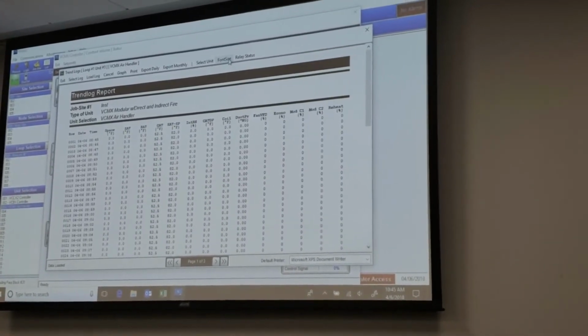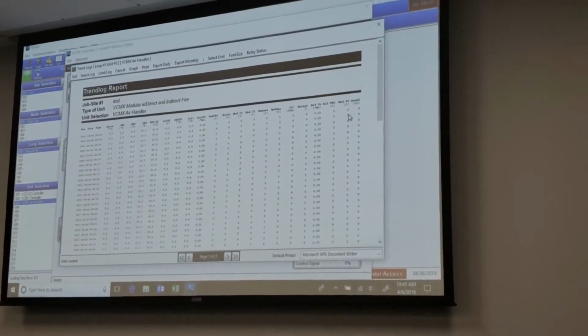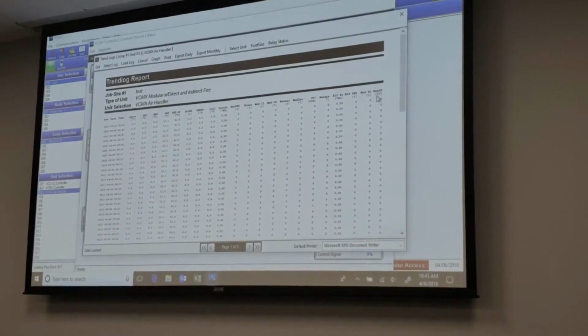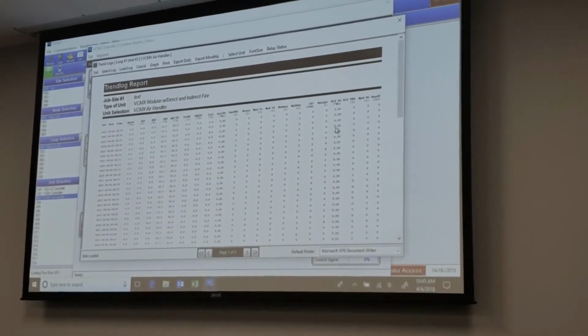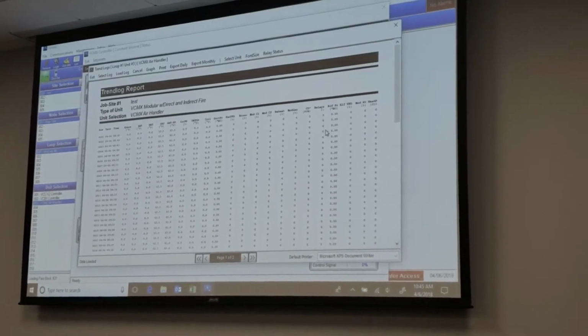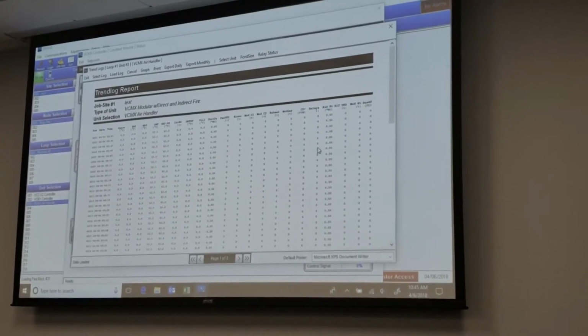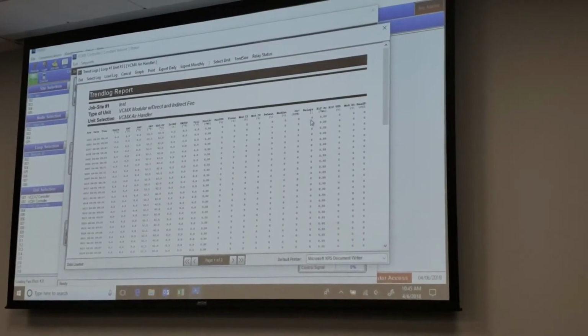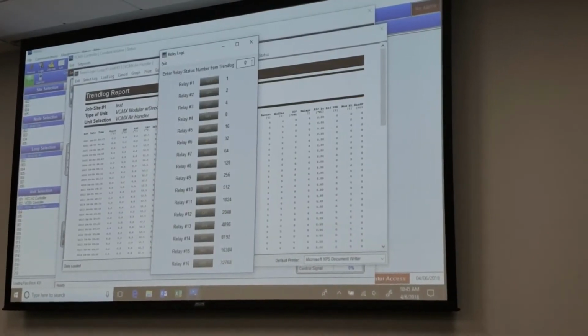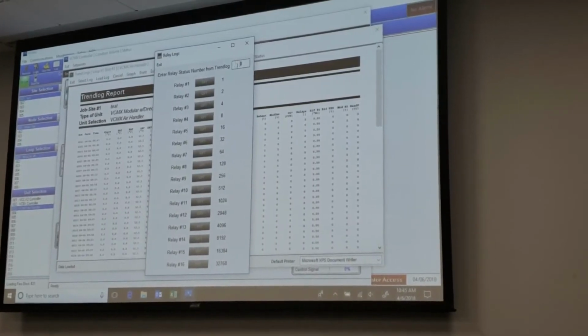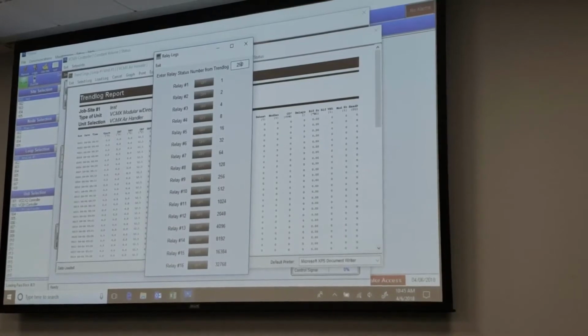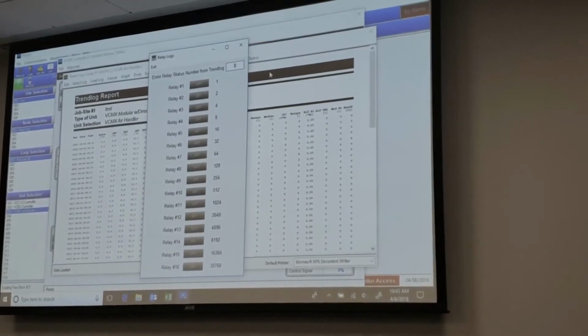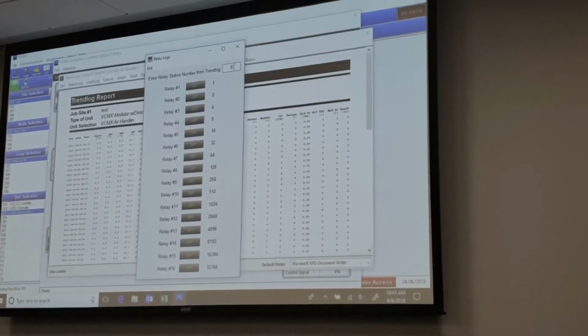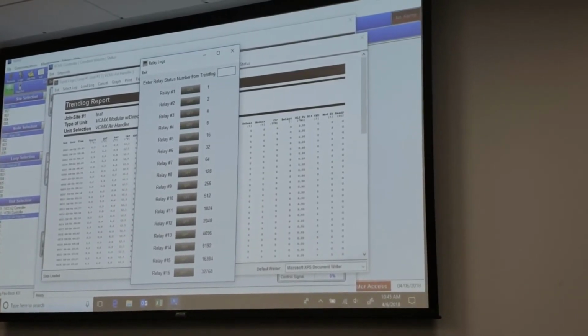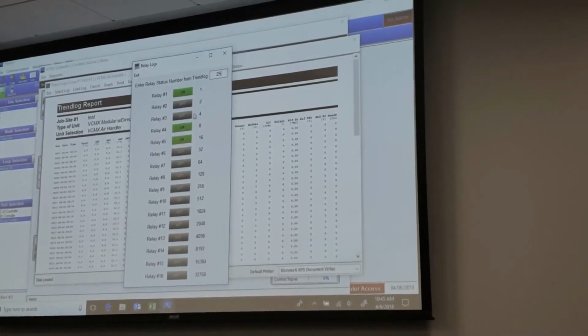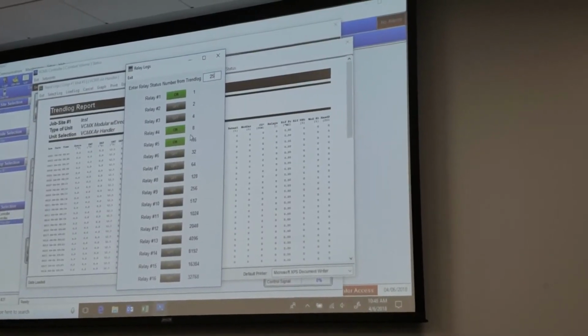Now what you can do is you can take the font size smaller on it. It's going to be almost impossible to see this far out, but it takes you all the way out to head pressure control. Now one thing that you can look at, which is cool, is the number for the relays. If you had relays that were lit up, you can just take that number, come up to relay status. Let's say there was a 25 in there, that it was reading 25. That tells me right there that relay number 1 was energized, relay 4 and 5.